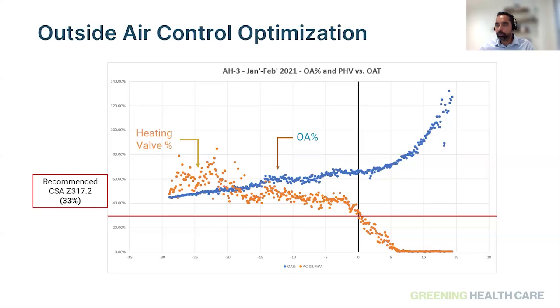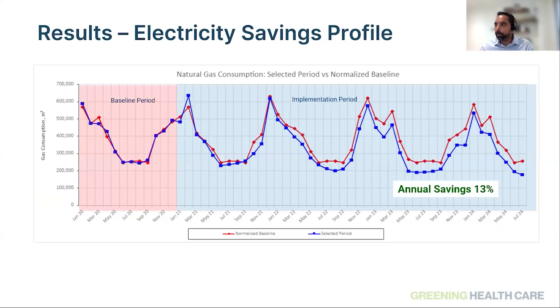And then this is again a simple measure, but when you track it, it has a huge impact on your gas savings. What is the minimum outside air requirement for the system, and how much are you actually bringing in? On this graph, the blue dots show the outside air percentage, and it was never close to the 33% required. Those were fixed as part of the optimization to ensure that when heating is on, you're bringing the minimum outside air, and the system could drift to economizer mode when not needed.